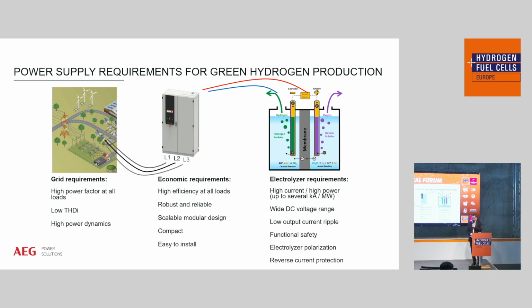In order to drive these electrolyzers from 0 to 100% of production capacity, you have to provide a large DC voltage window. On top of this, the DC current quality is also key, normally measured by the current ripple, which has to be low. Otherwise, the efficiency of an electrolyzer might go down, and it is also subject to aging.